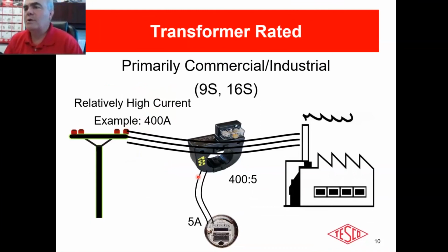Okay. So here's kind of a typical operation. You've got a 400 to 5 transformer, and typically you would have 3 of these in the line, one for each phase. It doesn't go directly into our meter; traditionally it goes through a test switch. The reason you have the test switch is that you can isolate the whole metering circuit very quickly, and you can interface all of your test equipment when you're going to test it in the field. And again, we'll see more about that next week.